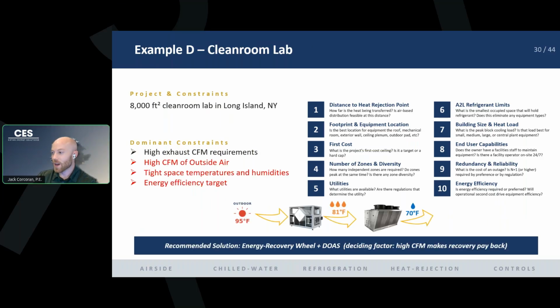We definitely need a DOAS, right? Because we have those tight temperature and humidities. But because we also have an energy efficiency target, why don't we add an ERV upstream of our DOAS unit, right? We can make a combined energy recovery wheel and DOAS unit. It's one unit that has both. Essentially that'll lower that temperature from 95 down to 81, and then your DOAS unit doesn't have to handle 95. It can handle that 81-degree temperature, so we can downsize it a little bit and save operational and energy costs on this system.